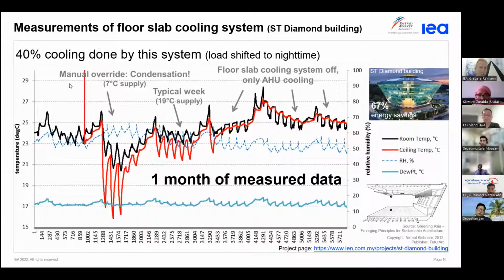But the week before, where they decided to override the operation, and where instead of feeding 19-degree water into the floor slab cooling system, they took the chilled water that's meant to go to the air handling unit, about 7-degree water, and then you can see you've got a big drop in the ceiling temperature, and we dropped below the dew point temperature, and that means water started to condense on the ceilings, and they were sort of raining indoors. So this is of course not the right way to operate it.